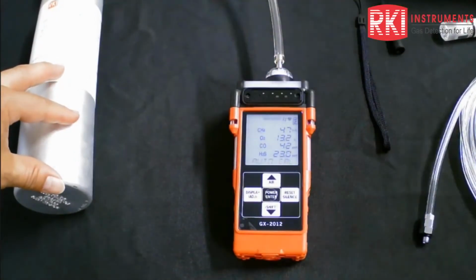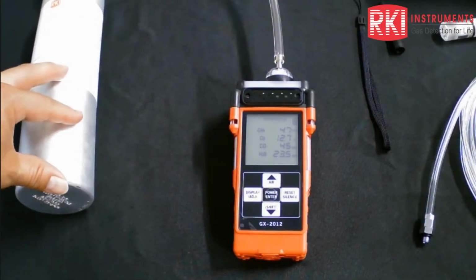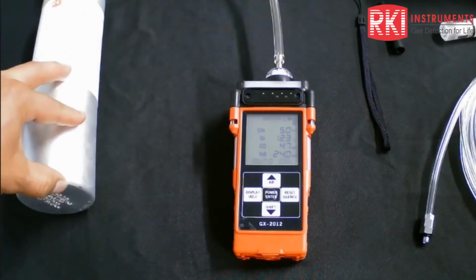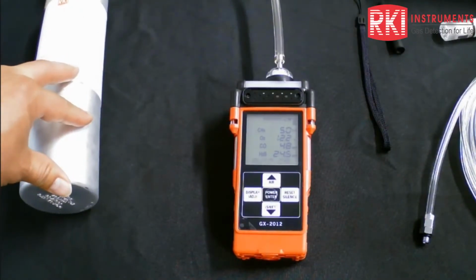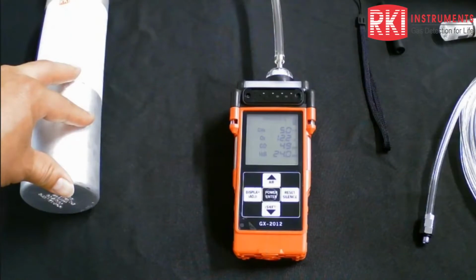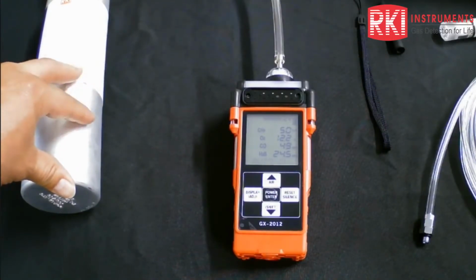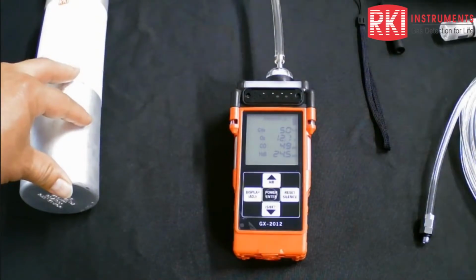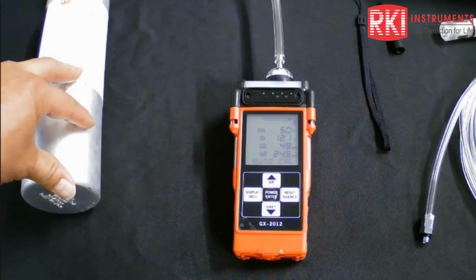All right, so we're going to let those readings climb up and stabilize. Our operator's manuals say to flow the gas for 2 minutes, but in reality, you really don't have to go that long. If they stabilize sooner than that, then that's sufficient. Okay, they're pretty quick. You can see how quickly they responded. So we're already at 50% LEL on the methane, 12.2% on the oxygen, 49 ppm on the CO, 24.5 ppm on the H2S. So we're really close, which we should be because I just calibrated this earlier before we started the webinar here.